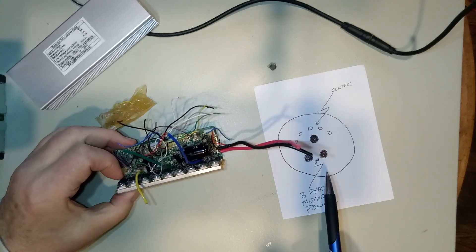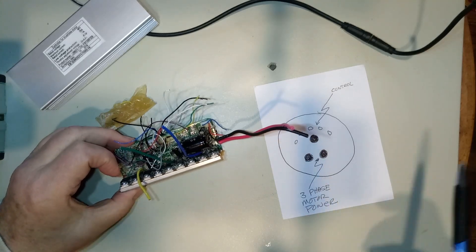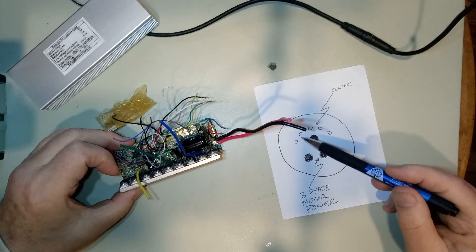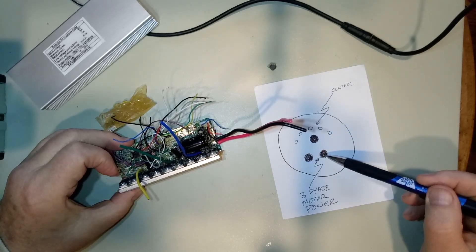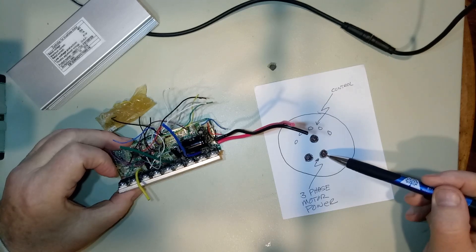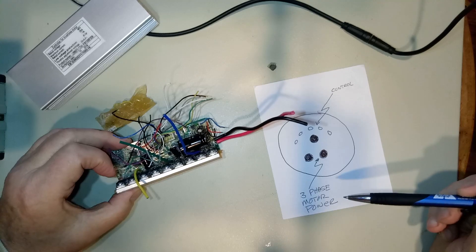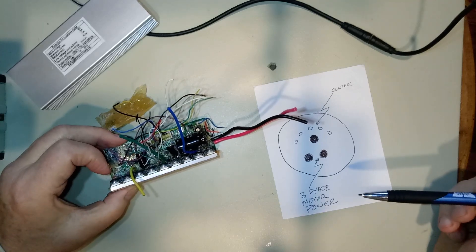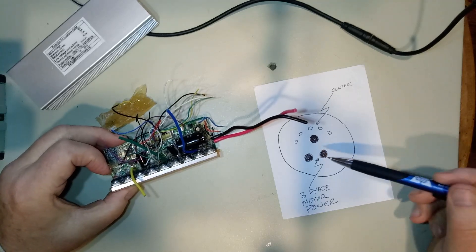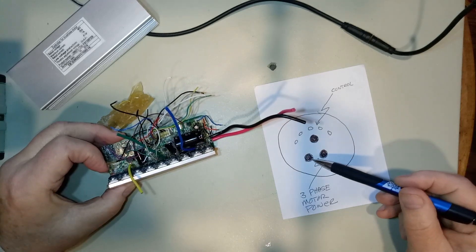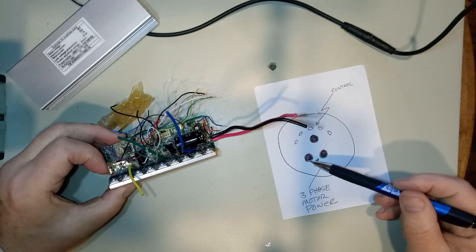I looked at the connector that went over to the motor. It has a bunch of little control pins on the outside and three big pins for the three-phase motor. Two of them were a real nice gold color, and the third pin looked like it was missing. It was actually still there but had really burned up. This was the problem.